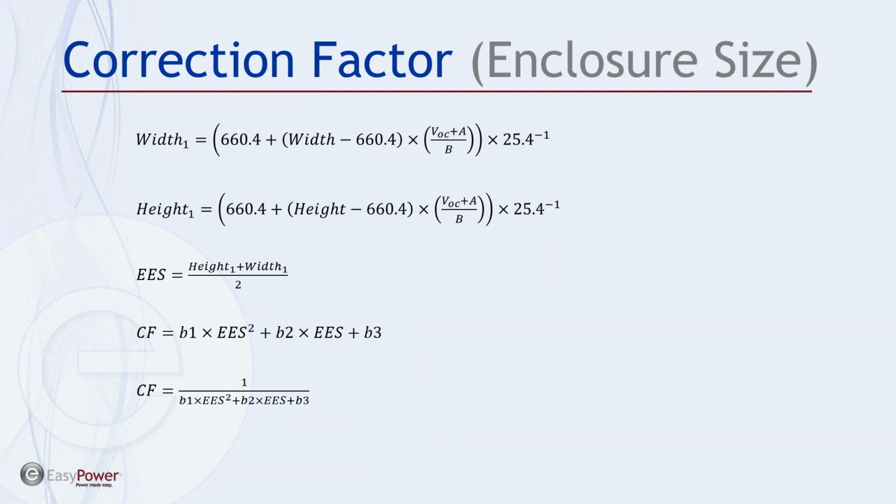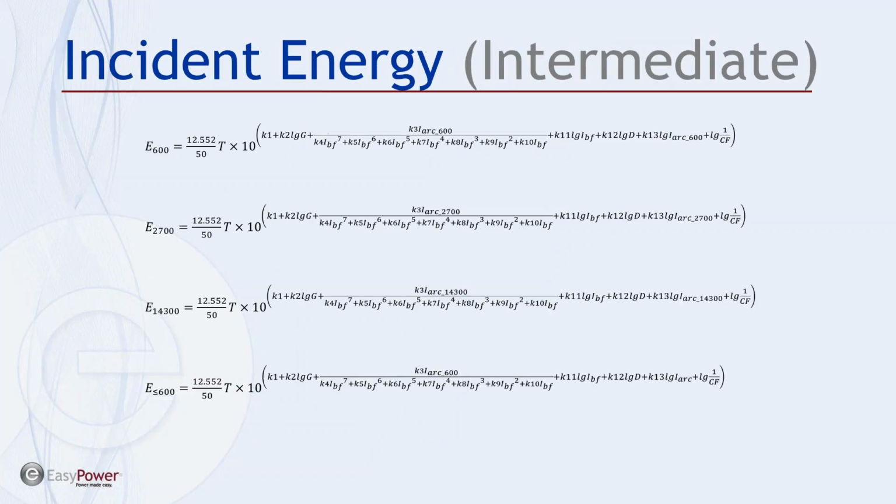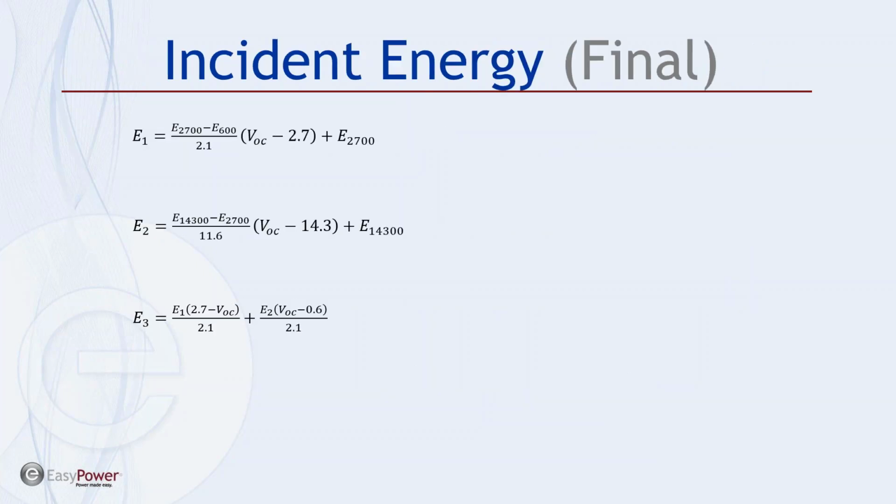And consequently, we go through multiple tiers of iteration and calculations, and then once we're done, apply specific correction factors based upon the type of equipment that we have. So what was a relatively straightforward calculation process using 4 or 5 equations, we now have something like a dozen equations that have to be reiterated anywhere from 2 to 4 times, and then correction factors applied to that, which pretty much negates the potential for being able to do this stuff by hand.